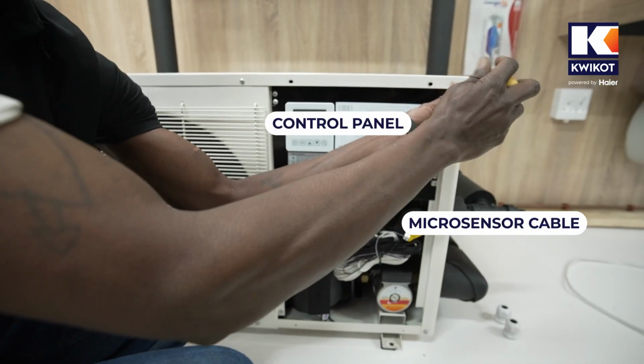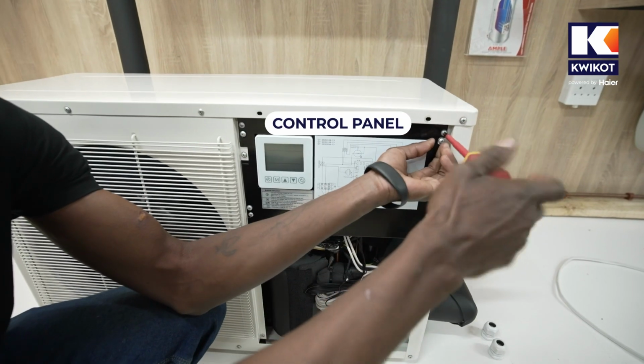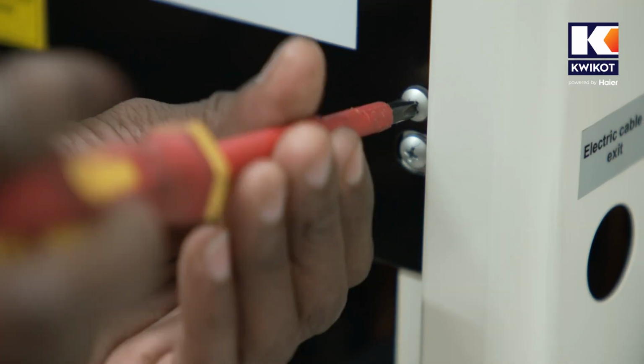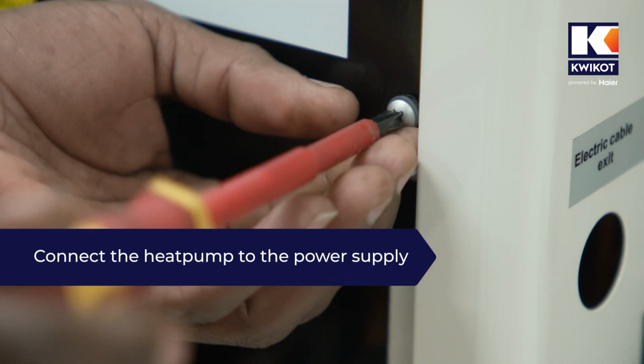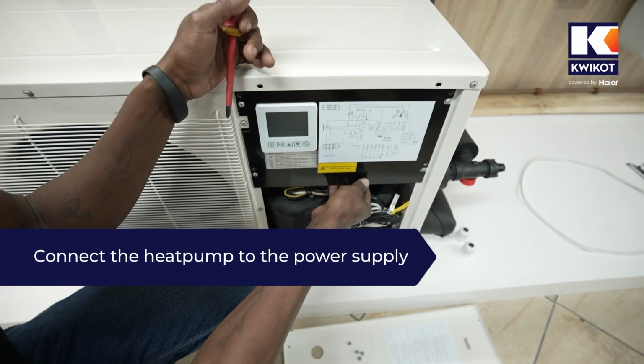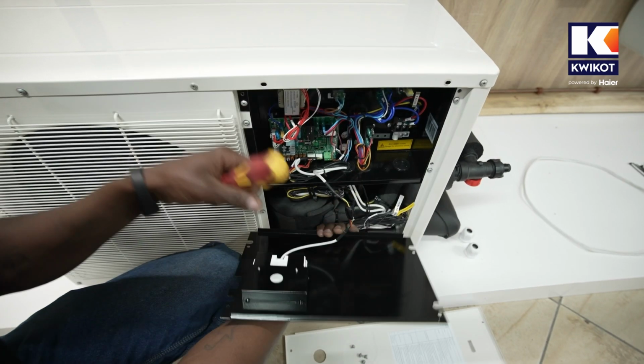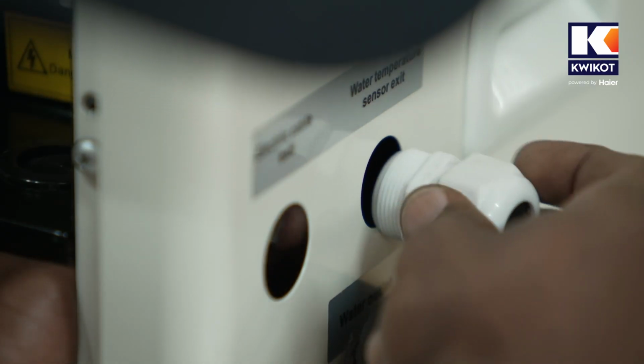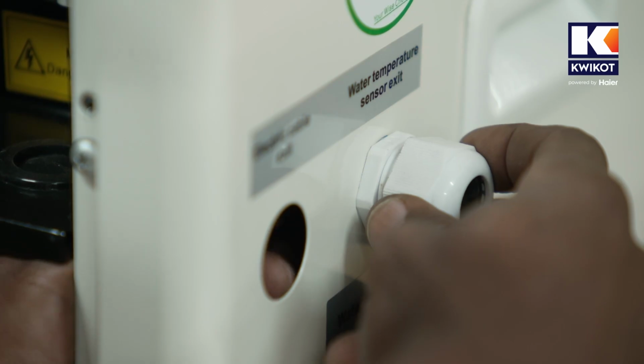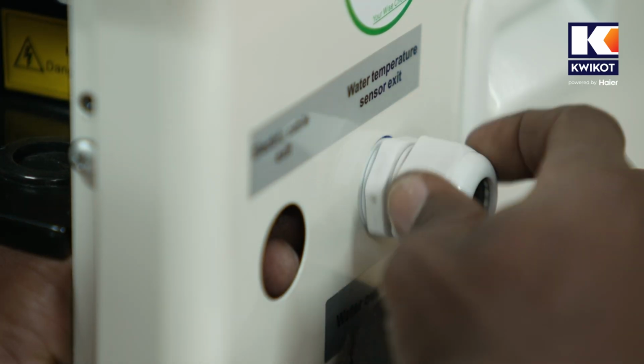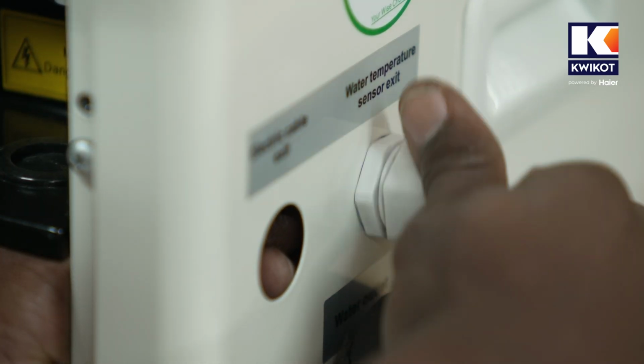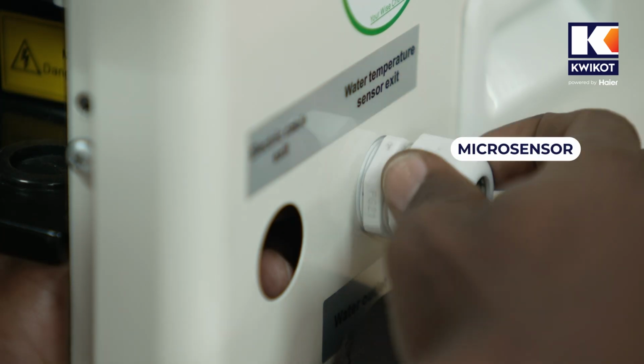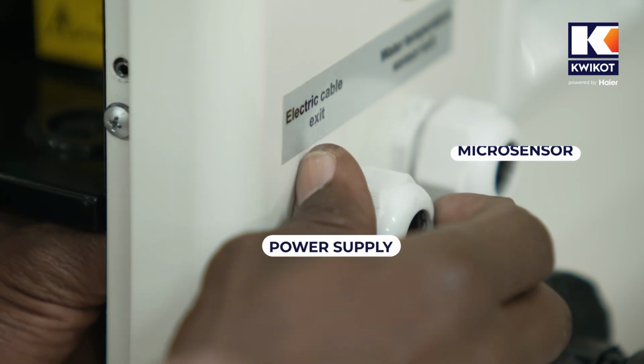Up at the top left is the control panel with a circuit diagram alongside. Next we'll unscrew and remove the second inner plate in order to access the wiring and connect the heat pump to the power supply. And for that we'll use our 2 glands and fit them onto these exits on the side of the box. These will hold 2 cables, a microsensor cable running to the water heater and the power supply cable.